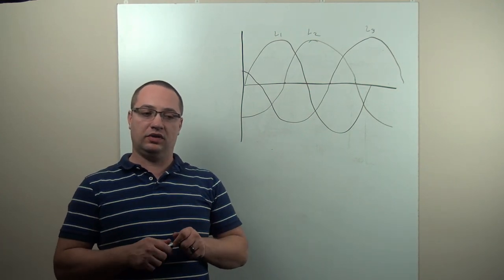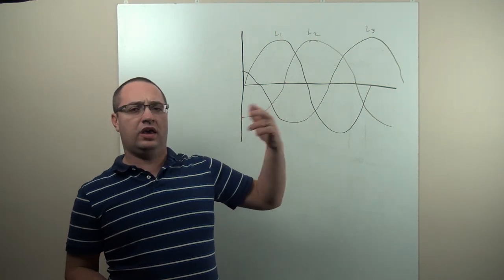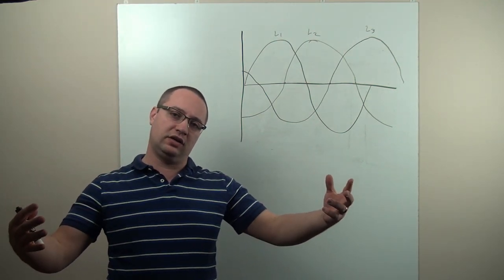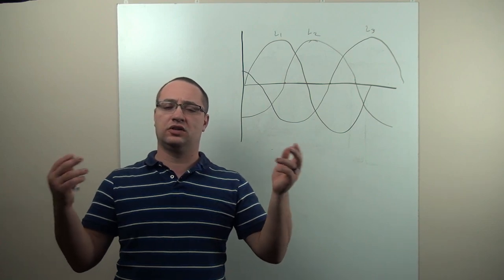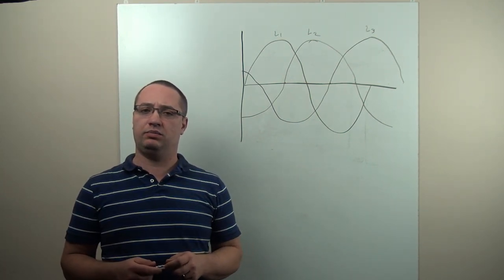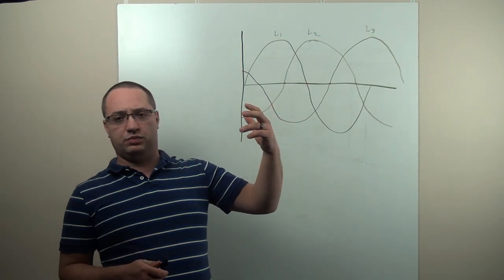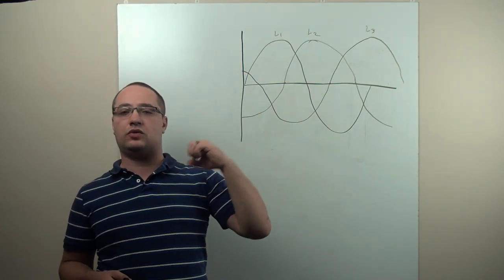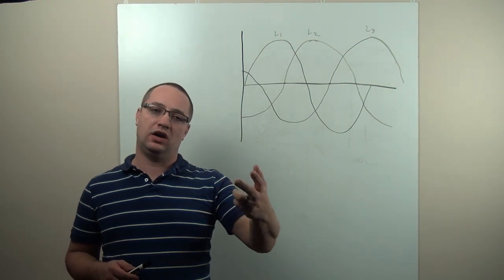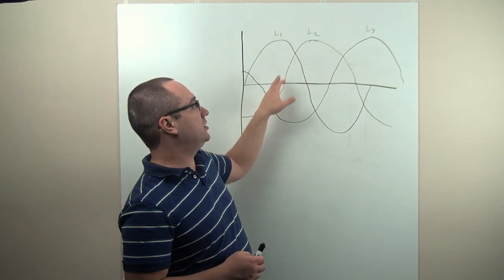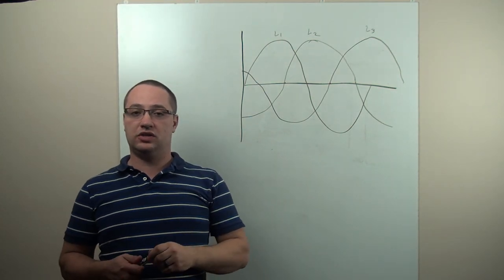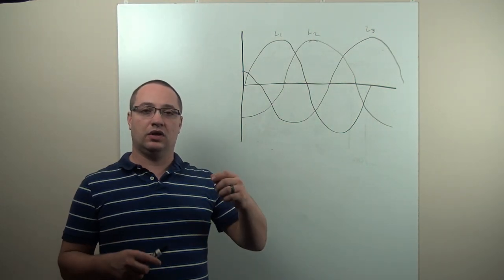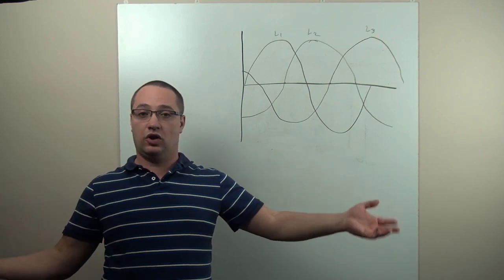Now, besides the obvious question that, well, hey, I have this large machine, it's the size of a small building, it's sitting in my warehouse, it's been hooked up for years and running correctly, why do I need a power quality relay? Well, having your phases swapped is only one thing that it monitors. For example, let's say you have a transformer outside and the transformer blows, unbeknownst to you. Well, you could have a phase, let's say L2, go missing, and now the machine's not going to run correctly, and so a missing phase will shut you down. This is in reference to large stationary equipment.